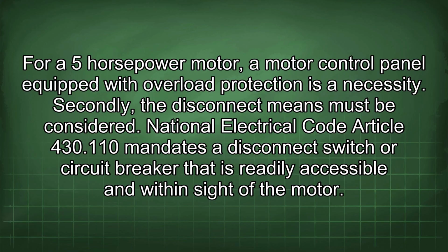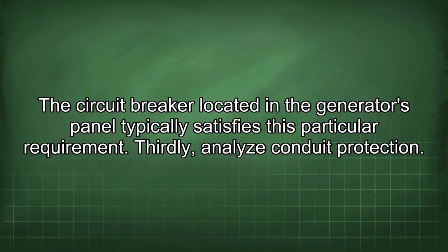Secondly, the disconnect means must be considered. National Electrical Code Article 430.110 mandates a disconnect switch or circuit breaker that is readily accessible and within sight of the motor. A circuit breaker located in the generator's panel typically satisfies this particular requirement.